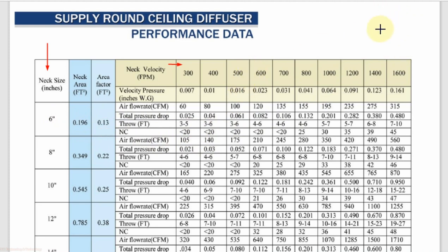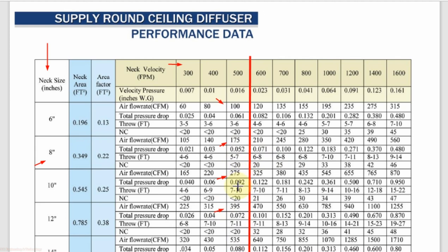If your duct is designed for a maximum neck velocity of 500 FPM, then you cannot go beyond this velocity to select the diffuser. After 500 FPM, for 6-inch neck size the maximum CFM will be 100 and the NC level will be less than 20 — very good. For 8-inch the maximum CFM is 175, for 10-inch it is 275, for 12-inch it is 395, and so on. When the NC level exceeds your requirement — suppose the maximum limit is 30 NC — then you need to select according to NC level.